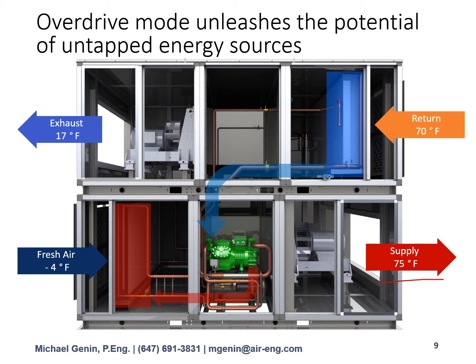Let's say you have an air source heat pump plant as your central source of heat. Well, back to our discussion, the average seasonal efficiency of that is about 4. And given that active heat recovery has a seasonal efficiency of 7, that can result in even further energy savings and cost reductions. So this is really the direction that we need to be headed in terms of heat recovery on the ventilation side: again, extracting as much energy as possible from that exhaust to produce as much heat as possible, to break the barriers of traditional passive heat recovery.